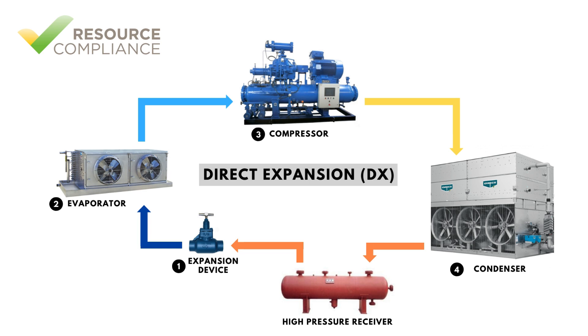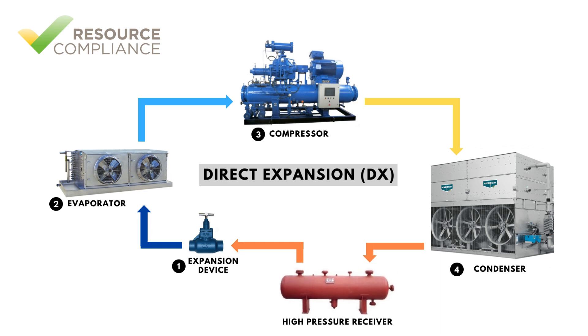Typically, the heat is rejected to the atmosphere. Inside the condenser, the refrigerant vapor is first cooled to its boiling point and then condensed at a constant temperature. The liquid refrigerant exiting the condenser typically drains into a high-pressure receiver.